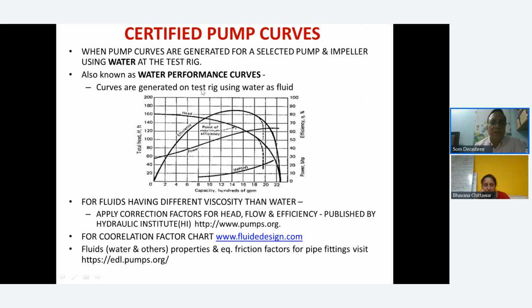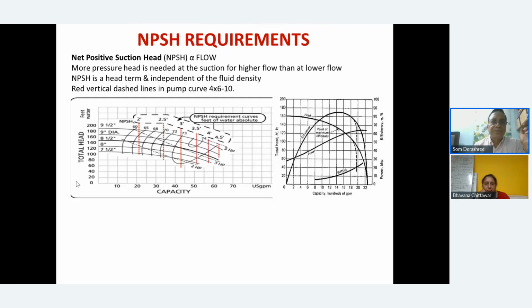These curves are only for water, because the manufacturer will test it only with water. For fluids having a different viscosity than water, apply correction factors for head, flow, and efficiency, published by the Hydraulic Institute, HI. You can go to this website, http://www.pumps.org, and the correction factor chart is at fluidedesign.com. These are the two places where you have to apply a correction factor to the certified pump curve if your fluid is different from water, because the manufacturer will give you only certified curves for water application.